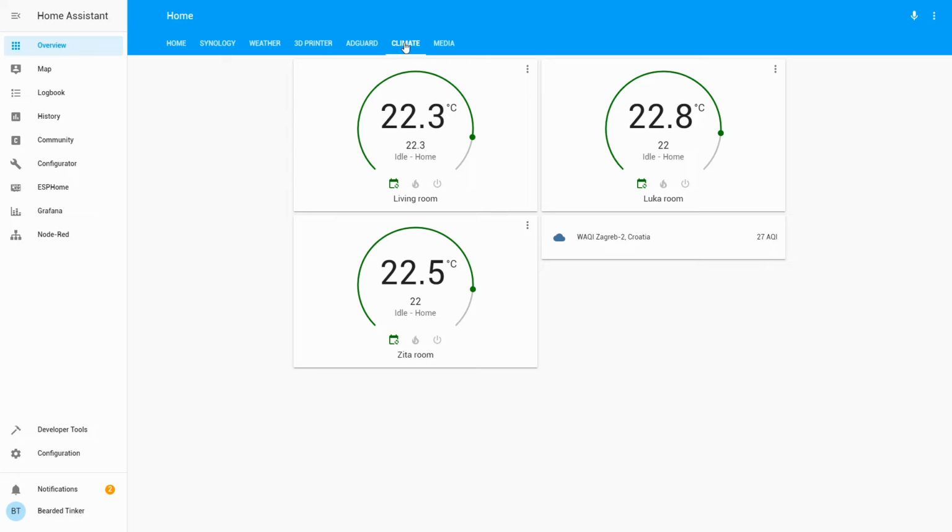And the result is the following. My home started to heat one of the kids' rooms. The battery in the smart valve was too low for it to open, so the valve was blocked. No heating was coming inside the room. The temperature sensor in the tado smart valve was dropping, and the application showed that my battery was good, condition was good. And it just kept on trying to reheat my room.